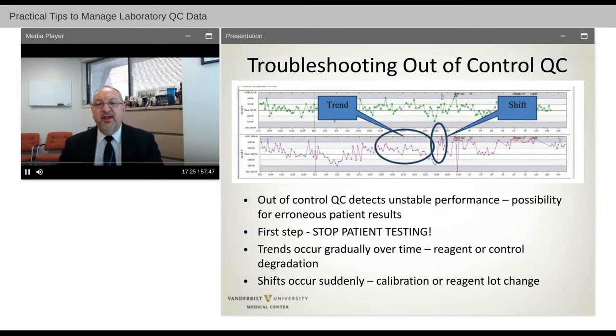As I'm looking at the monthly report, I'm looking at graphs. I look for shifts, which is a sudden change in the QC. I'm also looking for trends where it's downward or upward, downward as I've circled here in this plot. So a trend occurring gradually over time in reagent or control degradation, kind of pinpointing that this may have occurred, or a sudden shift where we may have shifted lots or we may have recalibrated that caused a shift in the performance of our analyzer and test method.